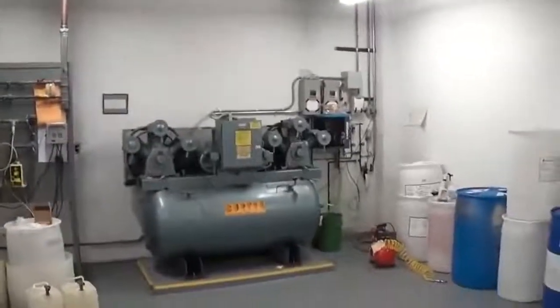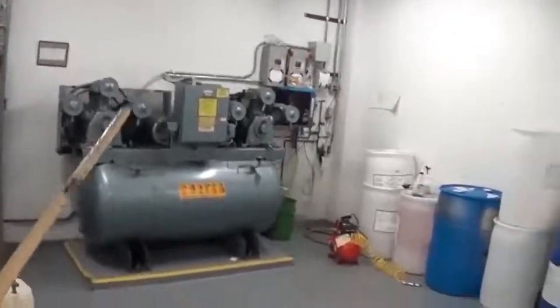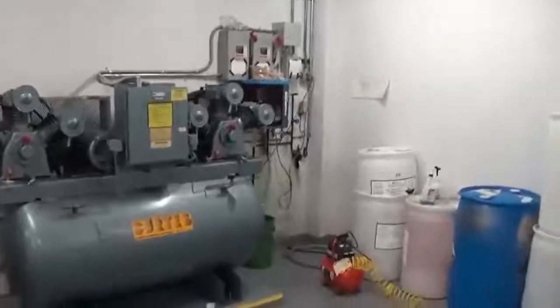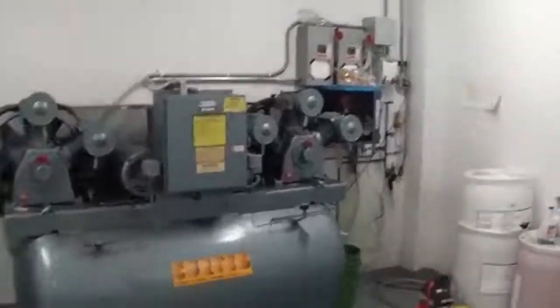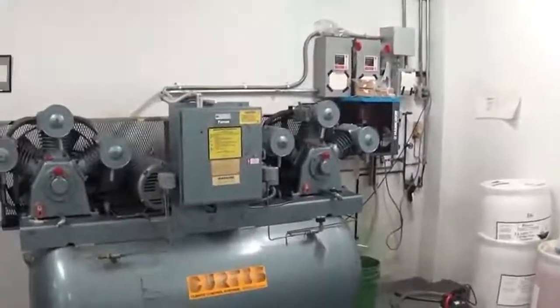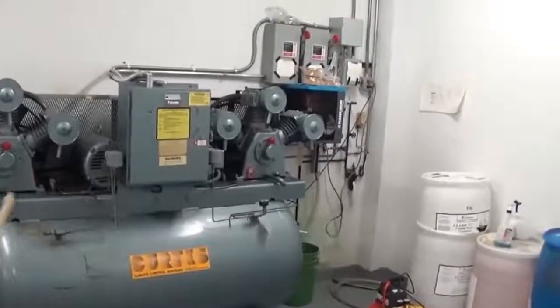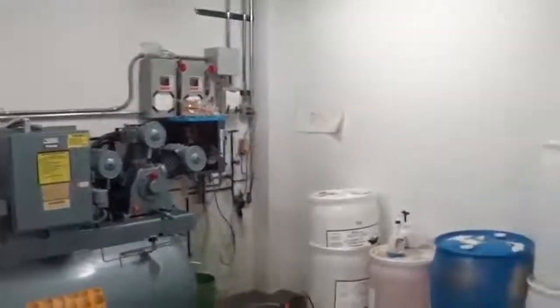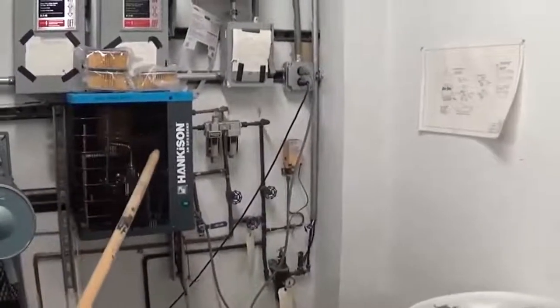So with the air valves, we have to make air. So we have a large air compressor here, which makes air for the chiller plant. As you can see, that is an old air compressor, but it's once more kept in immaculate condition by this crew here. To keep the air nice and dry, an enemy of pneumatics is moisture, so we have an air dryer, which is basically a refrigeration unit that dries the air leaving the compressor. Also removes some oil.